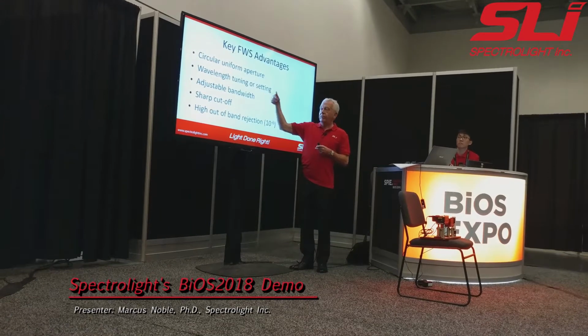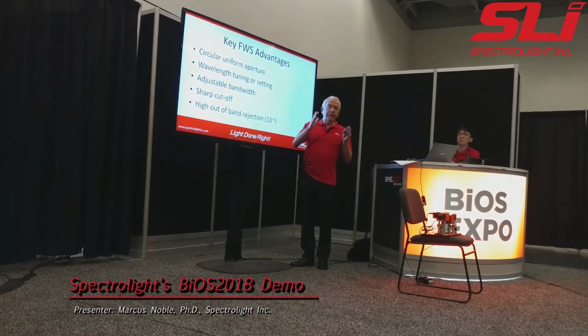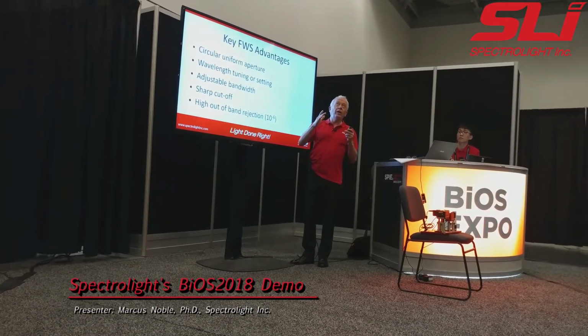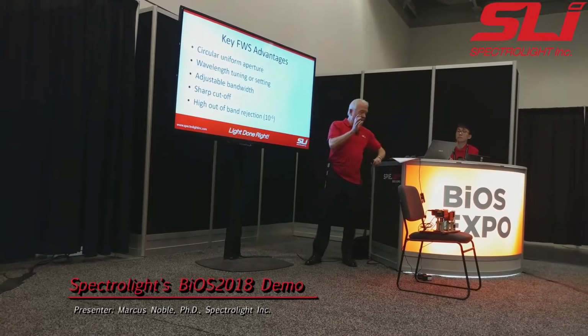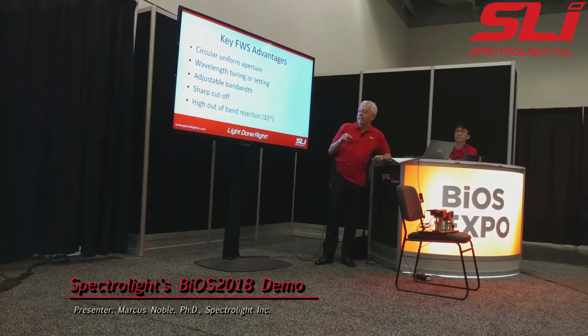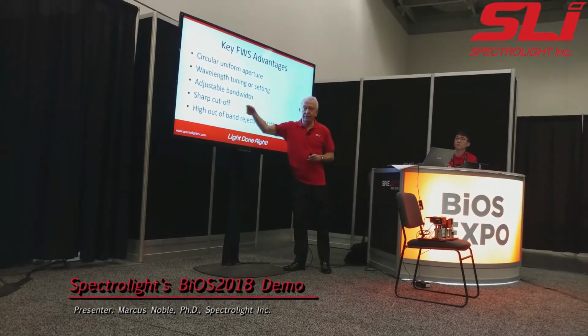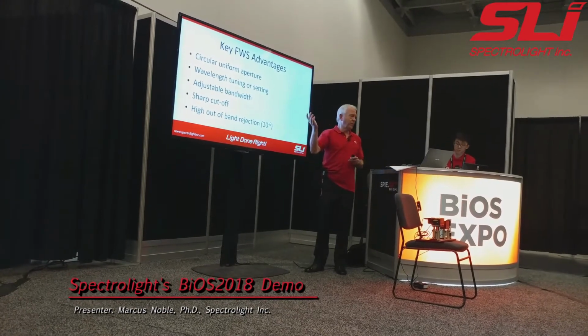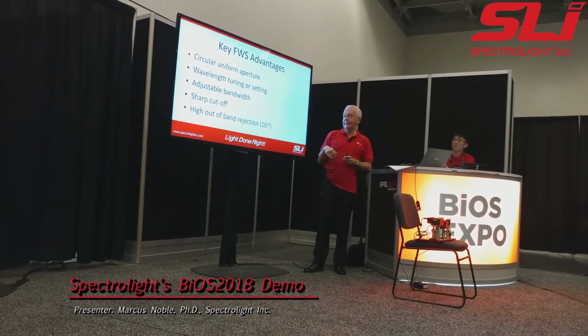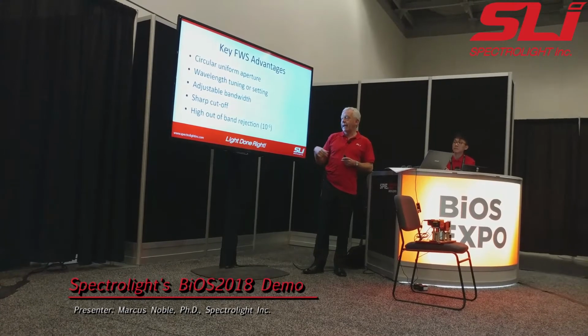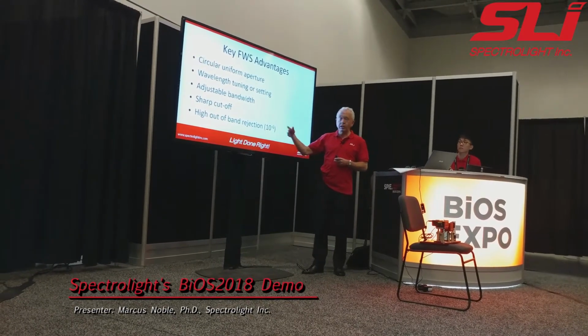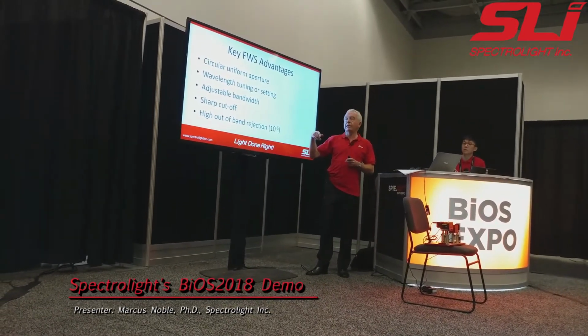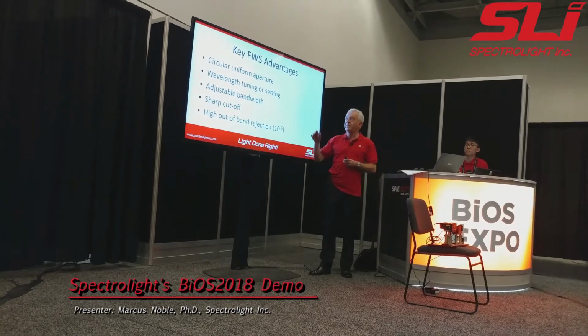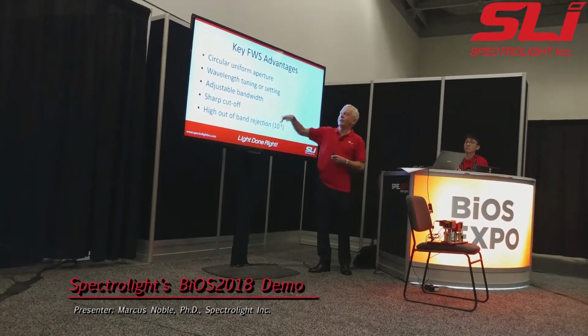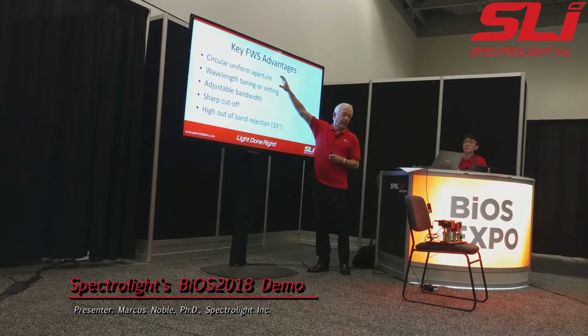Adjustable bandwidth, set it from anywhere from 1.5 nanometers, full width half max, all the way to 20 nanometers. Sharp cutoff, that's important if somebody was doing something like Raman or anything that involves a resonance. High out of band rejection, 10 to the 6th. So, much like a monochromator, but with a clear imaging aperture.